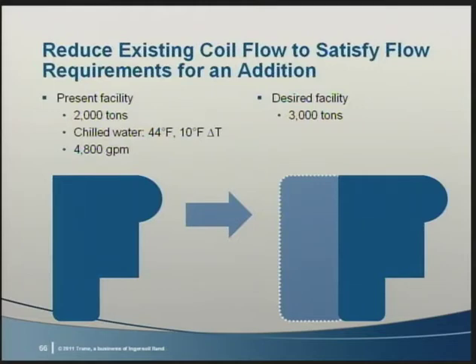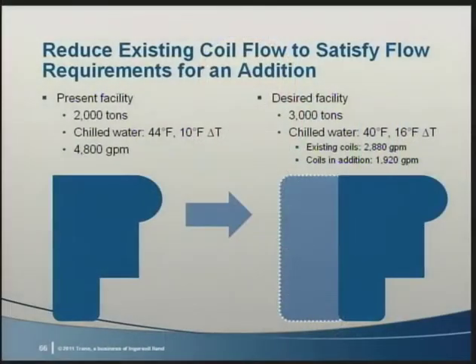To reduce the flow rate through the existing coils, we selected new chillers making 40-degree chilled water. This resulted in a 16-degree delta T at the air handlers. Now note that this 40-degree water temperature is a degree lower than our original example. That shows that it's important to reselect the existing coils to determine their performance, rather than using a rule of thumb. Now, use of the colder water reduced their existing coil flow requirements by 40% to 2,880 GPM. The rest of that water, over 1,900 GPM, was pumped to the new addition.